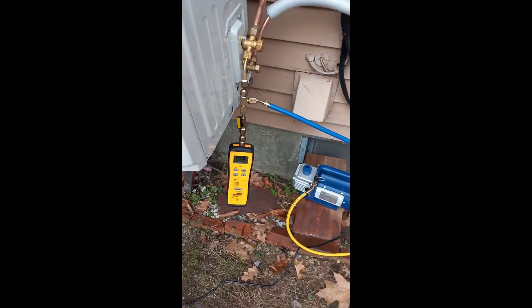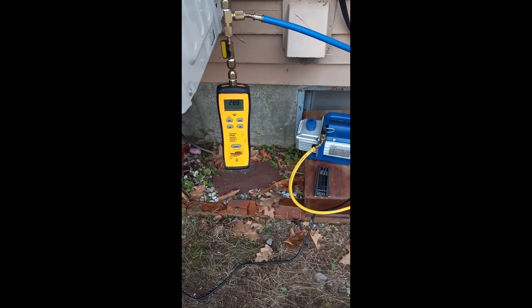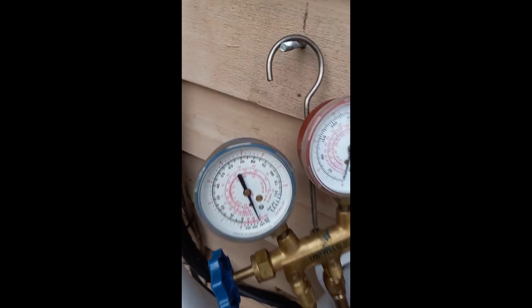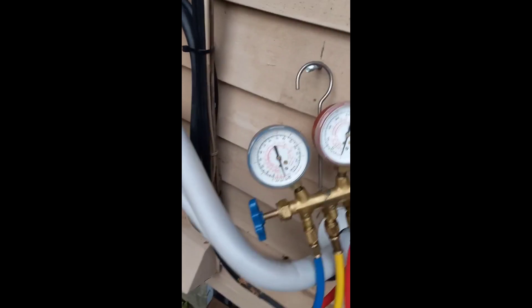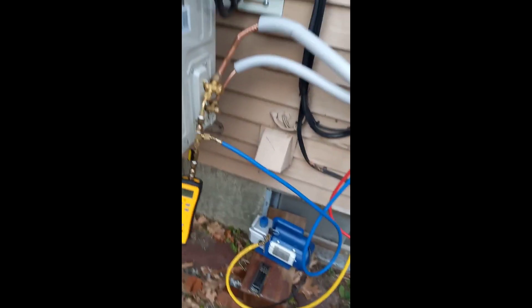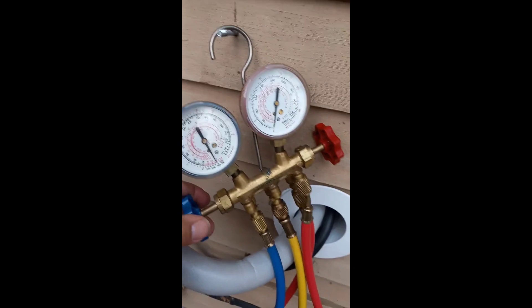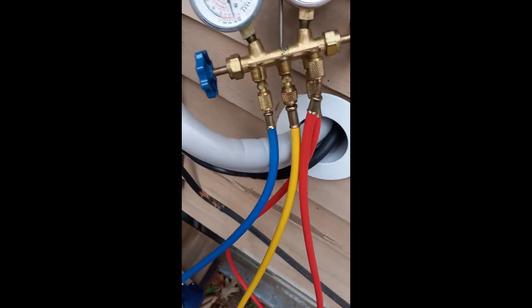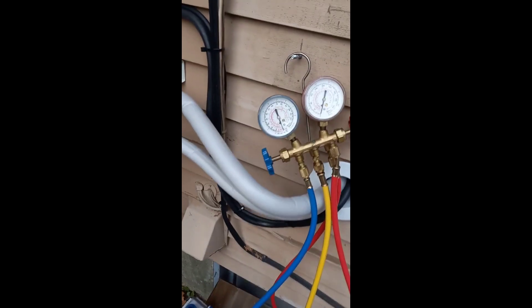We're getting down there — we're down to about 270-280 on the digital gauge, and this analog gauge here is nearly minus thirty. I think we're pretty good here; I've been vacuuming for about 45 minutes or so. I'm going to go ahead and shut the gauge off — hopefully without knocking it over — and then shut off the pump.